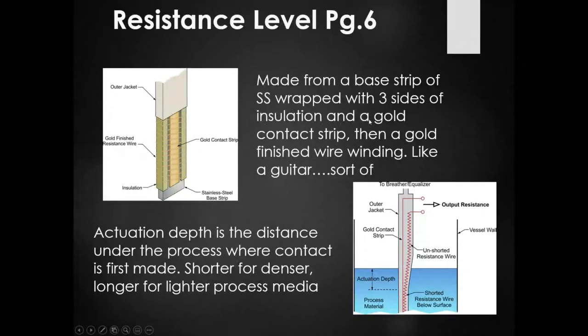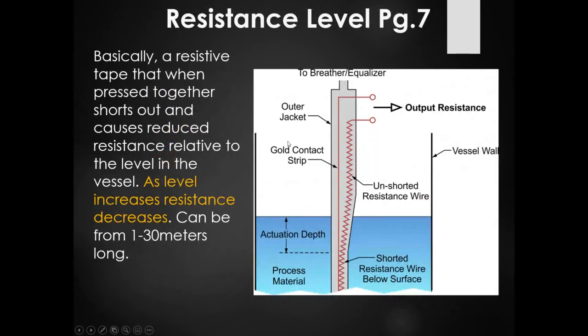The resistance tape is made from a stainless steel base strip wrapped with three sides of insulation, a gold contact strip, and gold-finished wire winding around it — like a guitar, sort of. As the tape is pressed together, it shorts out, causing a reduced resistance relative to the level in the vessel. As level increases, resistance decreases because we're shortening the length of wire. These can be from one to 30 meters long — which is why a silo is a good application.